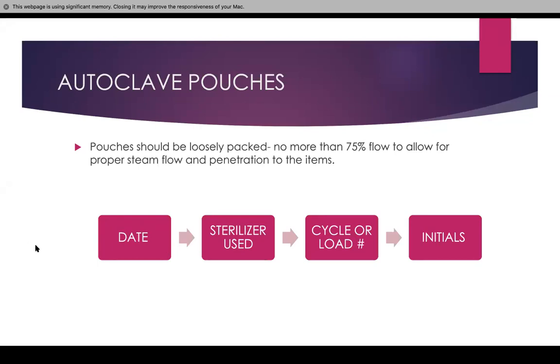The pouches have to be loosely packed — no more than 75% full — to allow for proper steam flow and penetration. What happens inside an autoclave is that the pouches are filled with instruments, and it has to heat to a specific time and create a specific pressure. The pouches are going to expand. If the pouches are too filled, they don't have enough pressure and heat going in them to expand, and therefore your sterilization is less effective.